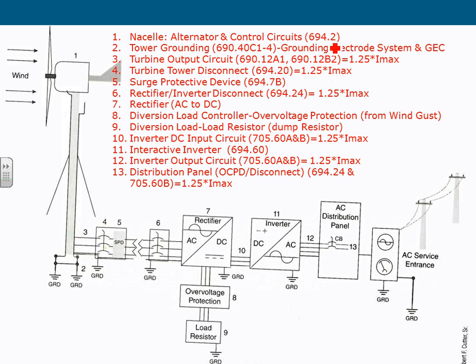When we size any system, if you don't know how to size a conductor, just use the number 1.25, and you are 90% of the time right. And by the way, even an overcurrent protection device, if you say 1.25, 90% of the time you're also right. So remember that number, 1.25, 25% extra. They put 25% extra for safety on it, and they size your conductors. And that would be the cables coming from the turbine down into the first disconnect means.